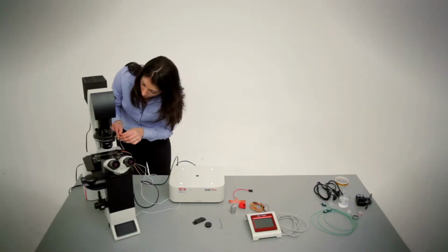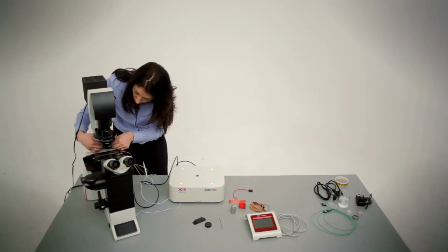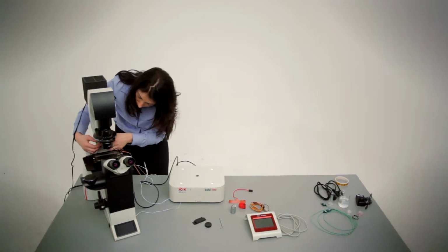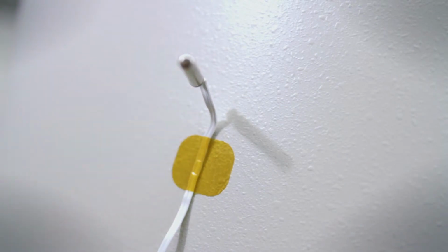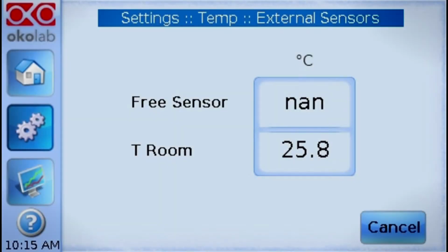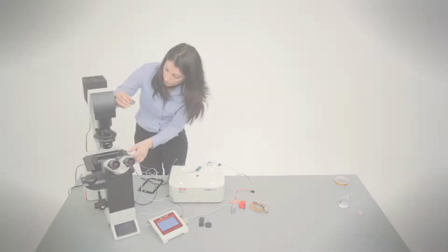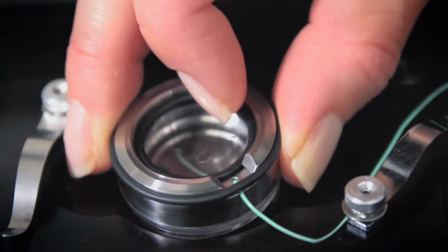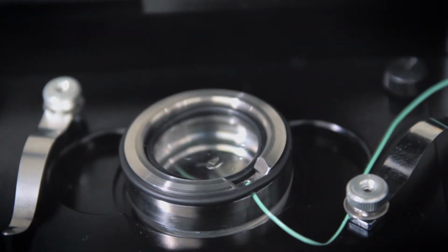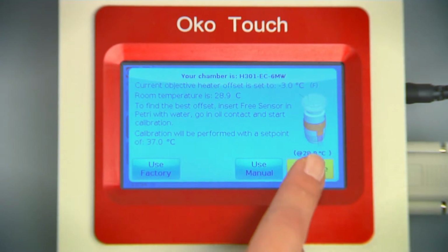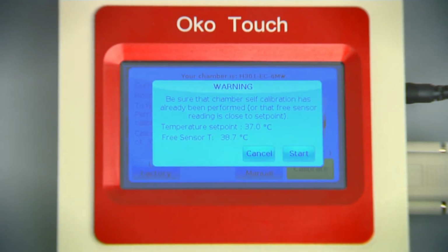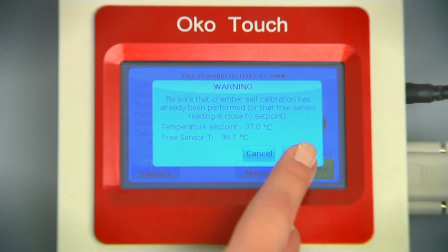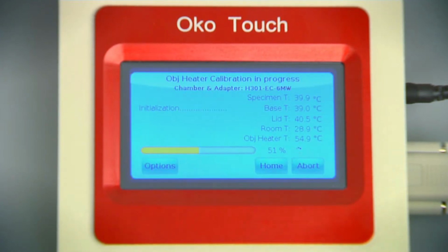The room temperature sensor, conveniently placed near the chamber, can be used to monitor room temperature. If room temperature is significantly different from 23 degrees Celsius, the chamber can be calibrated by introducing the green sample feedback sensor inside the chamber and performing the self-calibration procedure. Calibration data will be stored as a function of room temperature.